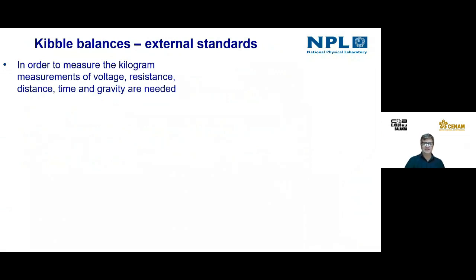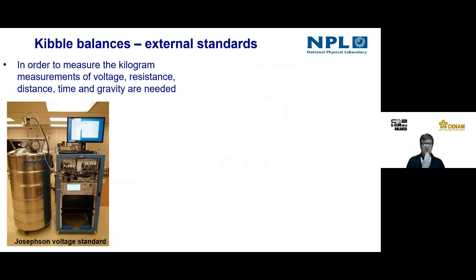Also, a problem with the kibble balance is you need external standards. So to measure voltage, resistance, distance, time, and gravity, we need what's called the Josephson voltage standard. This is a very, very complicated battery. It gives a very stable 1 volt or 10 volt voltage standard. But you can see it's a very complicated piece of equipment. And one of the big issues is it needs to run cryogenically at near zero Kelvin temperatures.